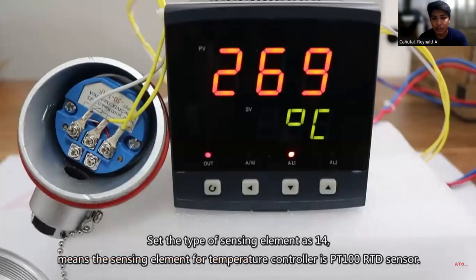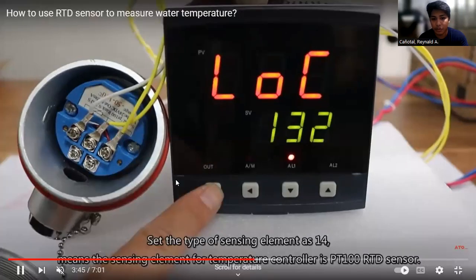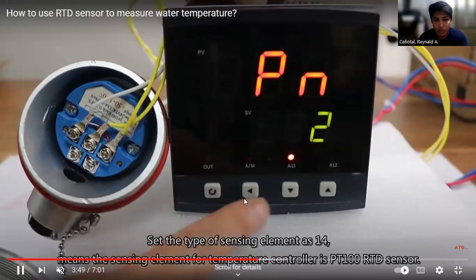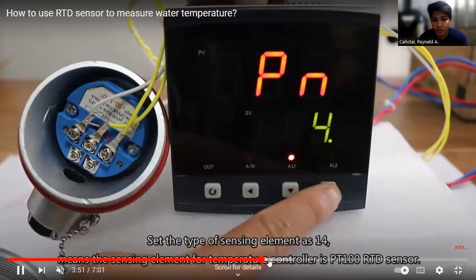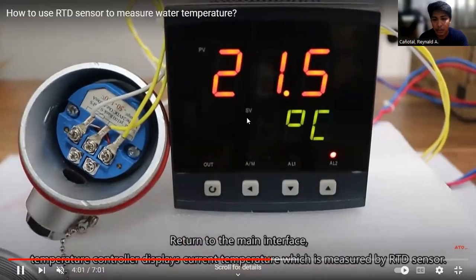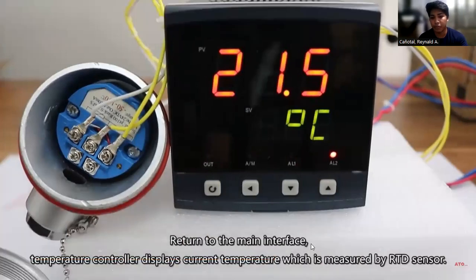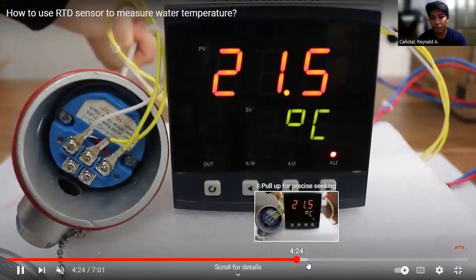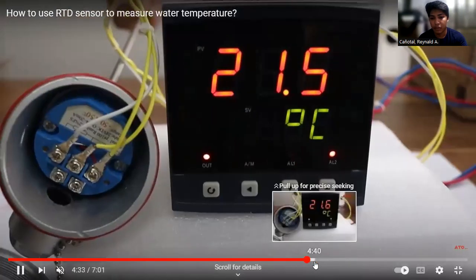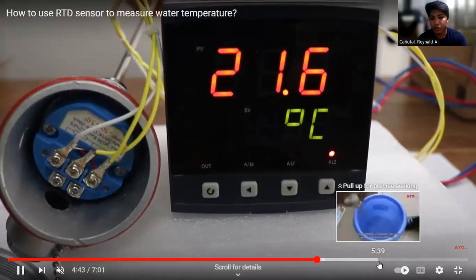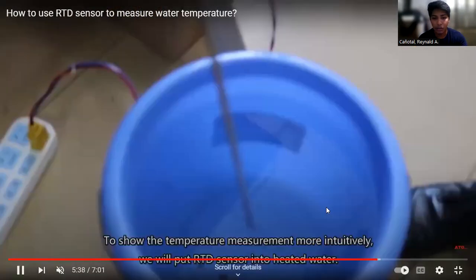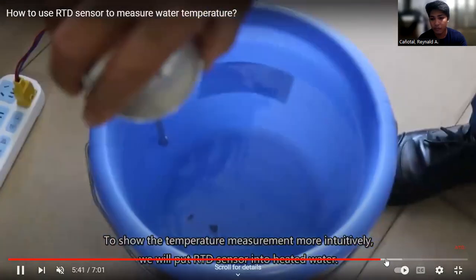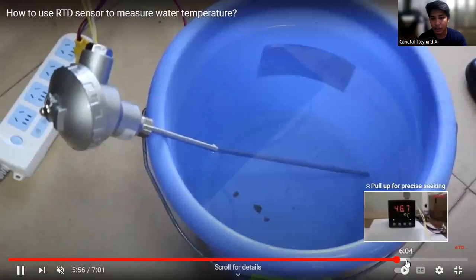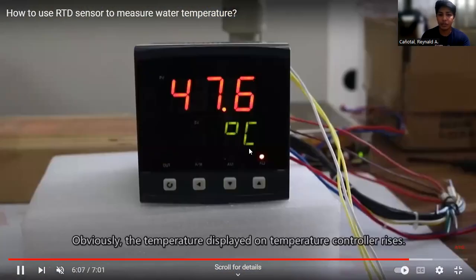And it said 269 Celsius. And he is going to calibrate the sensor. And now it is shown that the room temperature is 21.5. Eventually he is going to submerge the RTD in water. And the reading is 47.6.